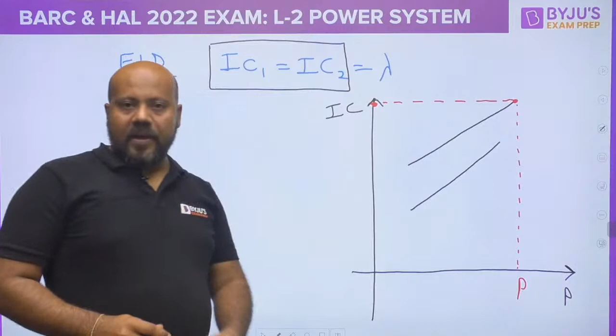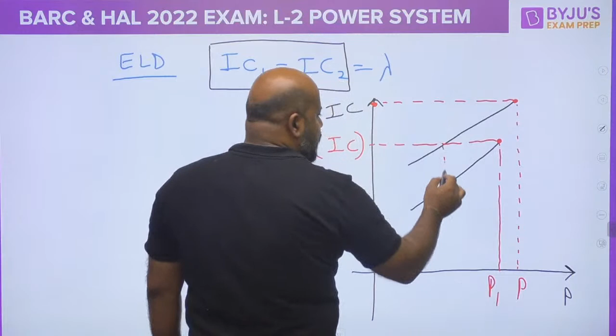Now I had to ensure the maximum power to be supplied to the load. Where will I start? I will start from this, because this gives me the maximum power supplied by this generating unit. But the problem is this operating point is not possible for the economic load dispatch, because for this power, this must be the incremental cost, and this incremental cost is not available for this generator.